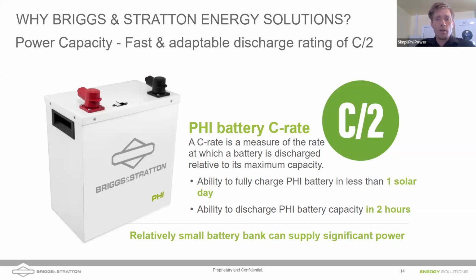We charge it at a current rate of C over 2, meaning the full capacity of the battery charges in 2 hours, which allows our batteries to provide relatively high power output for limited size batteries. It also lets you run the generator a shorter amount of time — if you're charging up in 2 hours, you want to charge quickly and turn that generator off when doing generator charging.